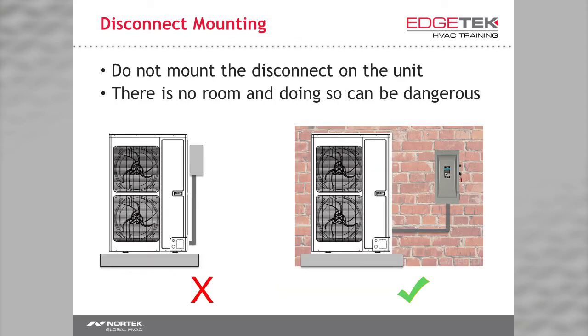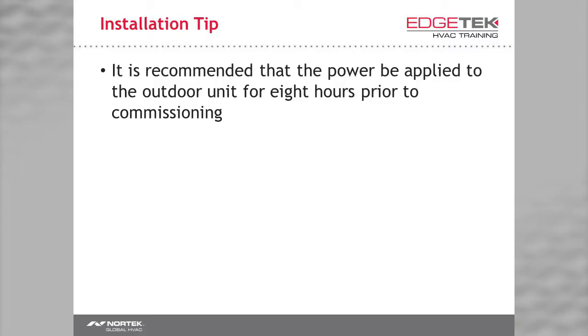There is no safe area to mount your disconnect on the equipment. Please don't try it. Mount on an adjacent wall in accordance with local codes. We'll cover this a little more later, but let's go ahead and talk about it in case you're watching this on the job. Your outdoor unit has to have power for 8 solid hours prior to commissioning.